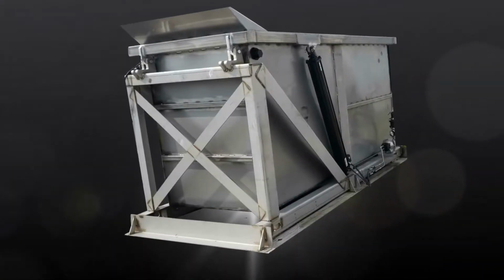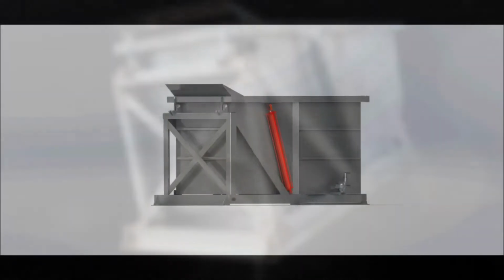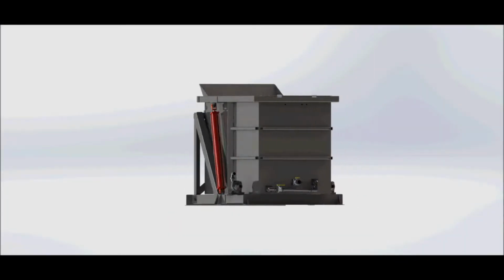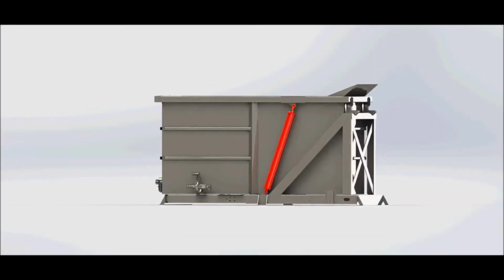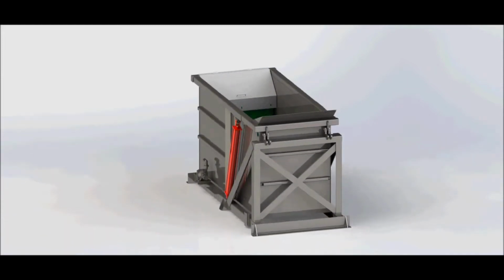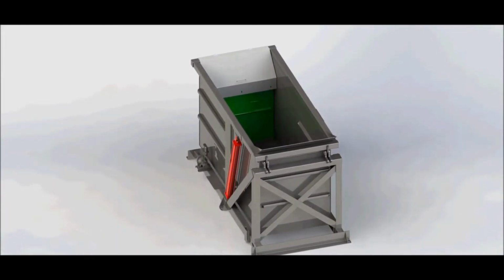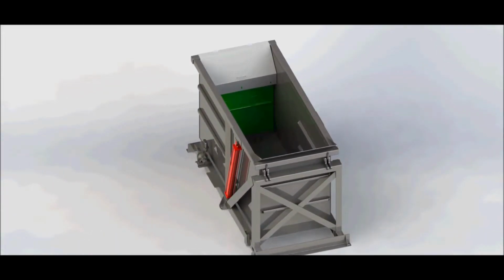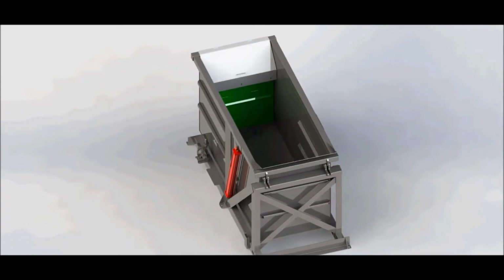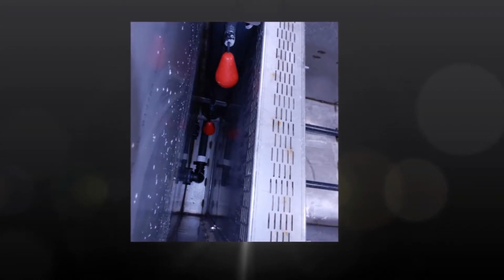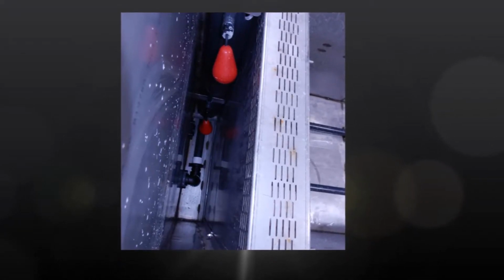The heavy gauge stainless steel hopper and frame provide outstanding corrosion resistance and durability. The improved hopper design integrates a baffle inside the hopper that makes a secondary sump tank unnecessary for salinity and water level monitoring. The previously external floats have been relocated behind the baffle. The upper float senses maximum liquid level, the lower senses the minimum required for recirculation and salt fill activities.